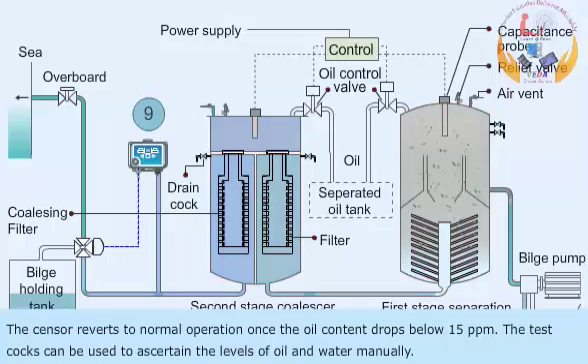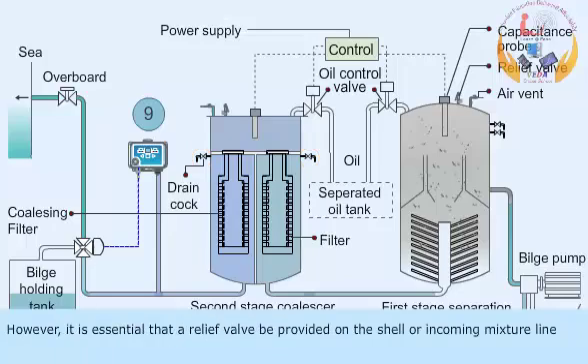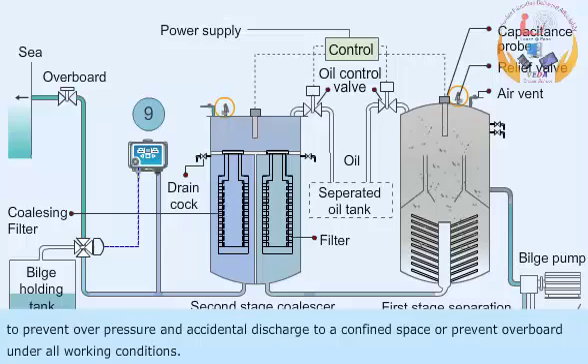The sensor reverts to normal operation once the oil content drops below 15 ppm. The test cocks can be used to ascertain the levels of oil and water manually. A spring-loaded valve is usually fitted on both discharges. However, it is essential that a relief valve be provided on the shell or incoming mixture line to prevent overpressure and accidental discharge to a confined space, or to prevent overboard discharge under all working conditions.